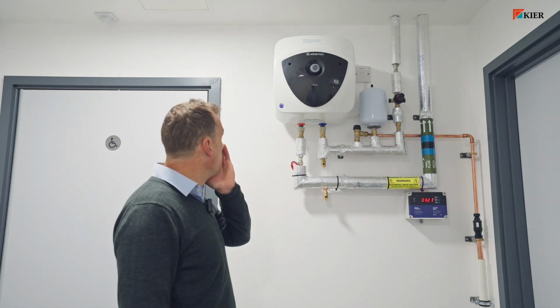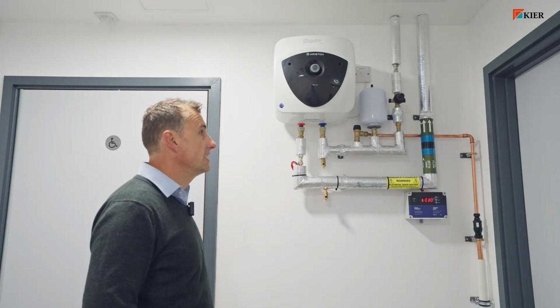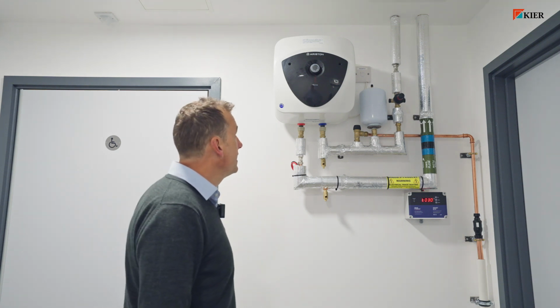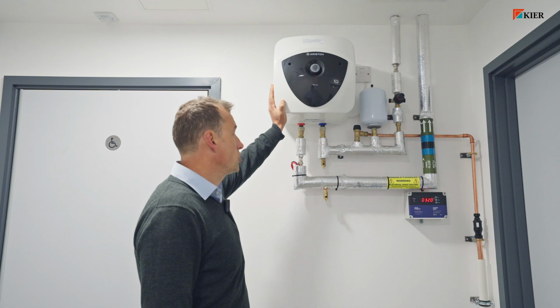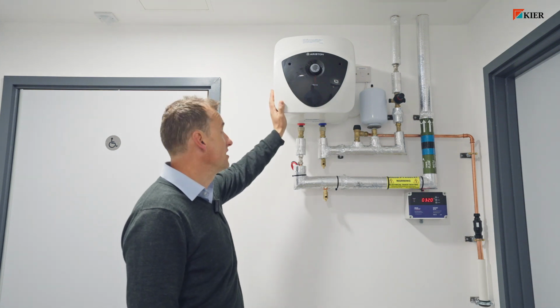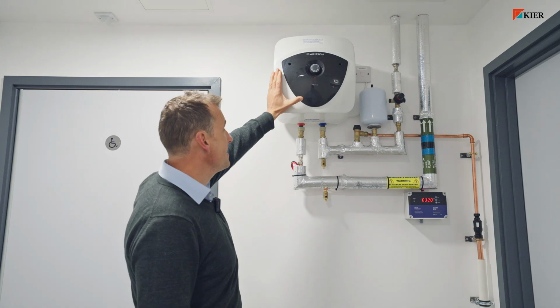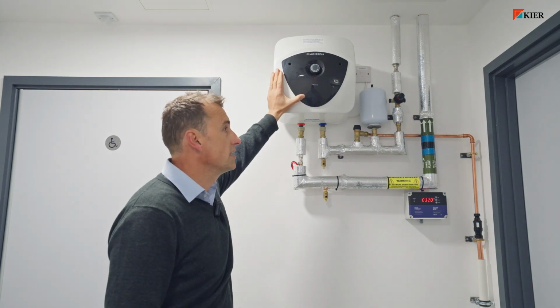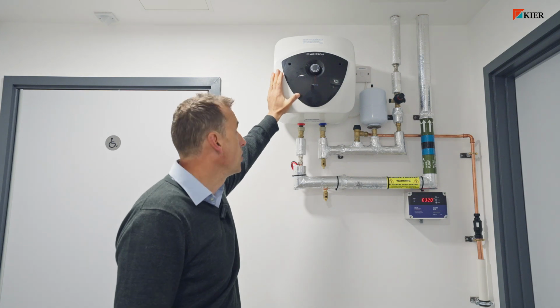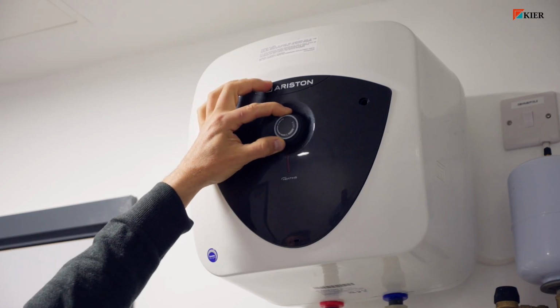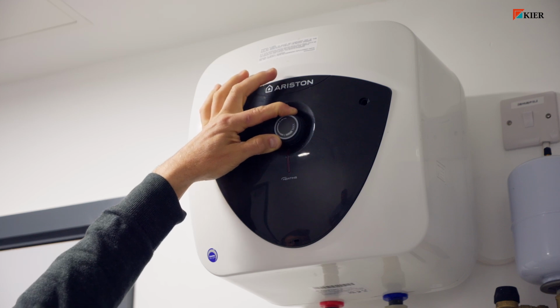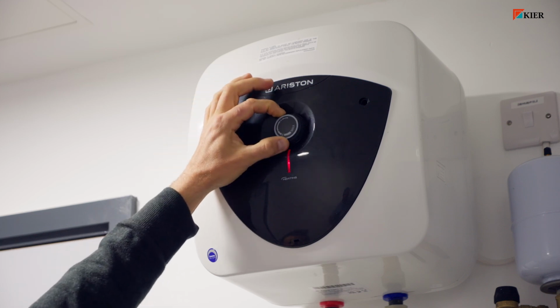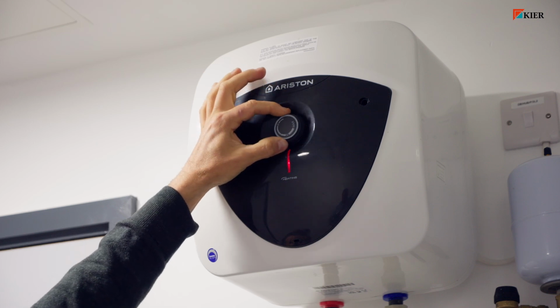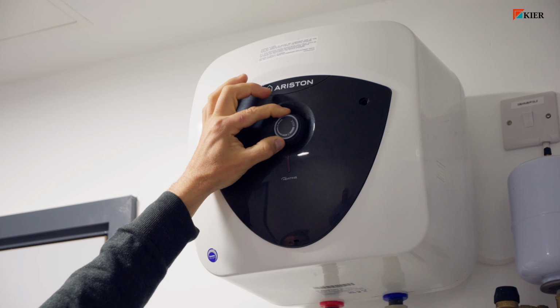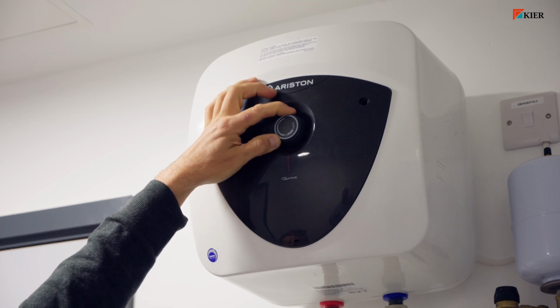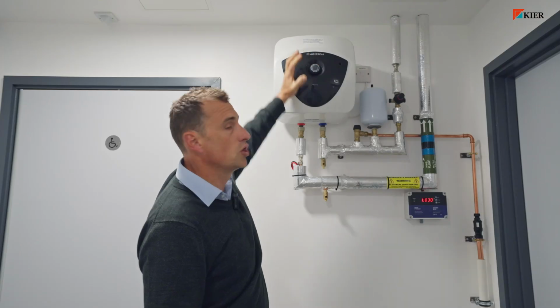This demonstration is for the water heaters. So there are 3 water heaters. One is located in the cleaner's cupboard, one in this location in the driver's changing area, and there is one in the kitchenette under the sink. These have all been pre-set up already. If you do find that the water temperature is a little bit hot, a little bit too warm, or a little bit too cold, merely just a minor adjustment on this switch over here, and that will then adjust your water. So that way over there is for max, and coming back this way over here is to get your minimum. In order for that to work, it's just a very minor adjustment. As I say, these are all already preset, so they shouldn't need any adjustment.